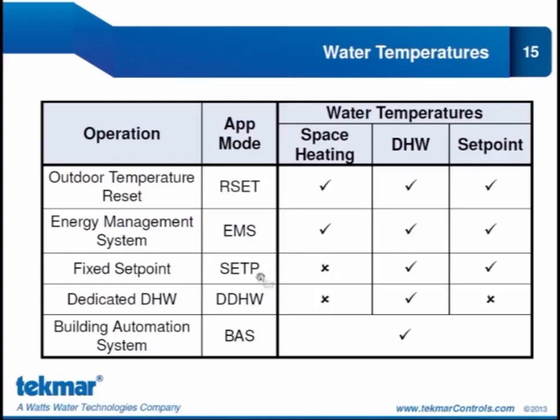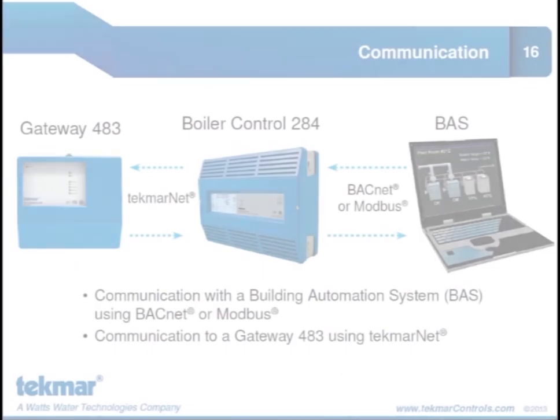If we're in fixed set point application mode, we can't do space heating, but we can do our set point operation and domestic hot water. In dedicated domestic hot water mode, we can only do domestic hot water. That is the only water temperature that we can configure. And in building automation system mode, we receive input for a single water temperature, and that water temperature could be used for anything. It could be used for set point or domestic hot water or space heating.